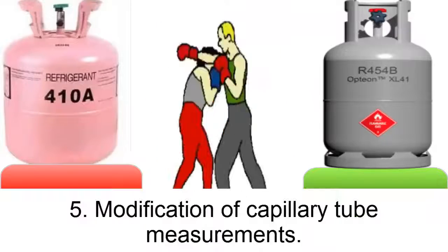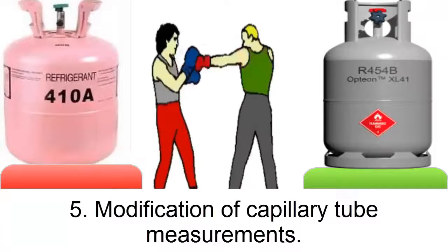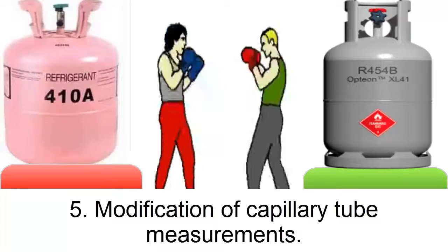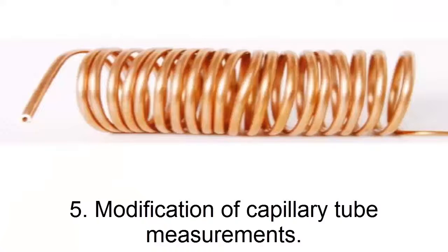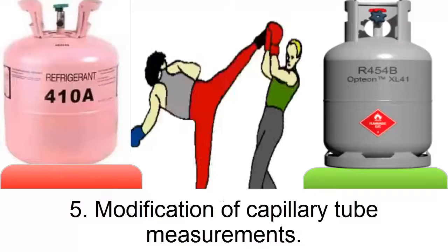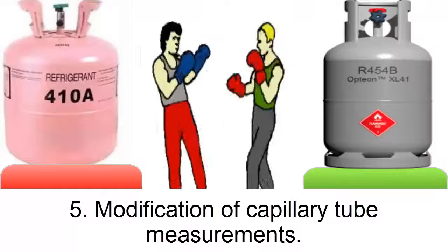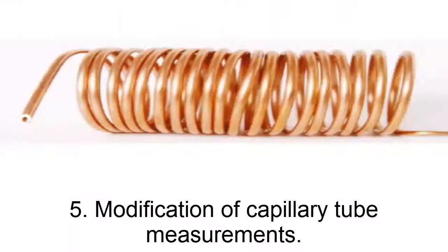5. With a higher density, R410A might require a slightly smaller diameter capillary tube or adjustments to its length, as there is more mass per unit volume. Therefore, to maintain adequate flow and avoid efficiency or performance issues, slight modifications to the capillary tube may be necessary.